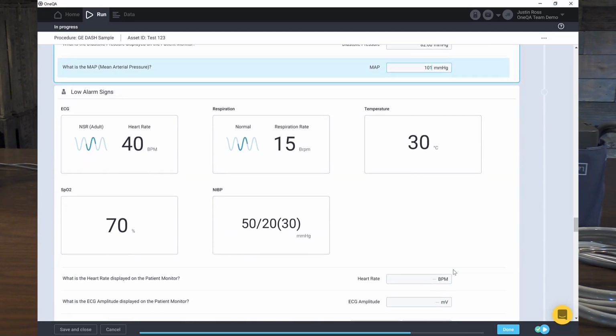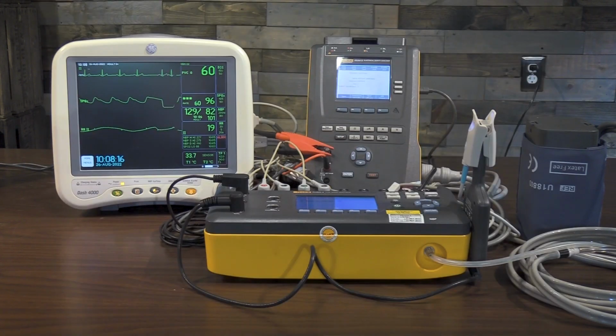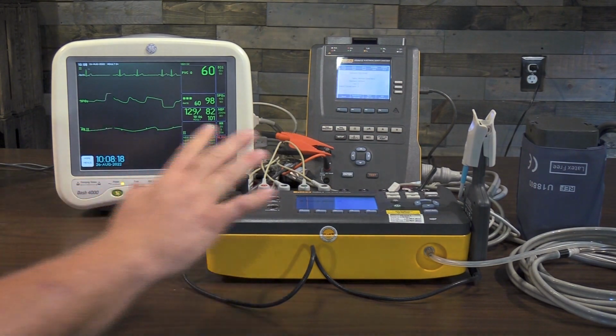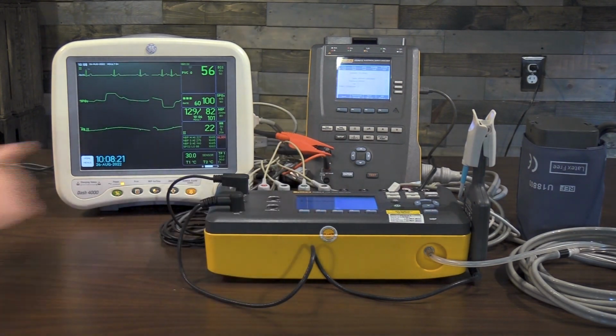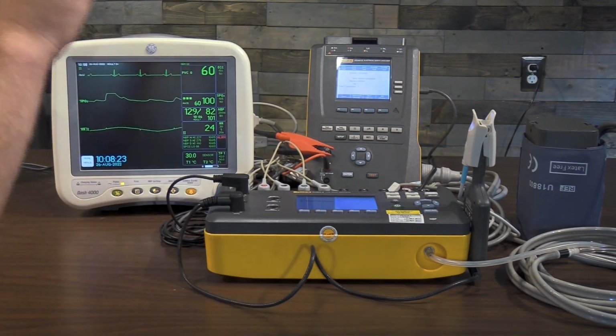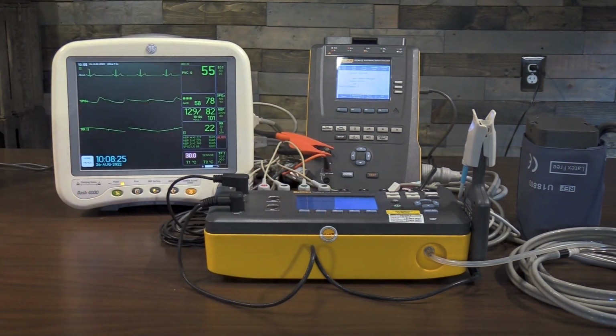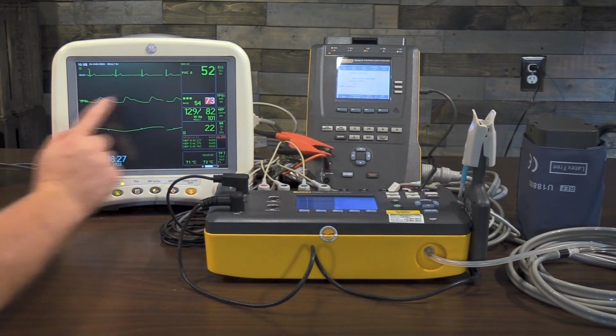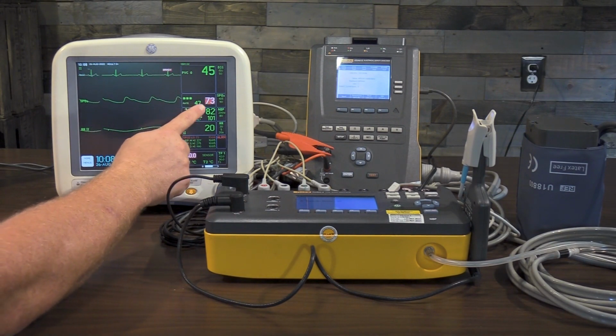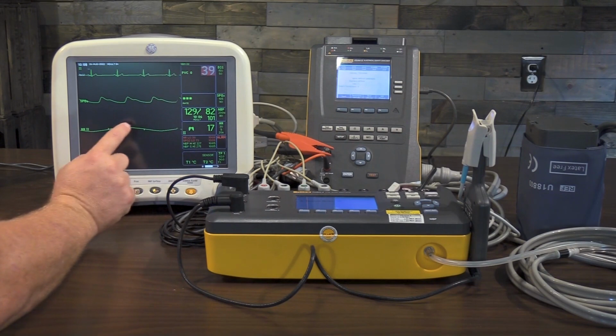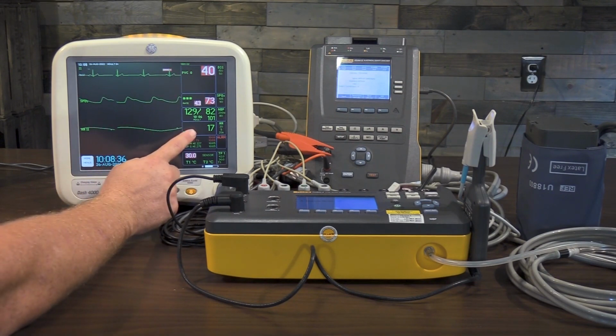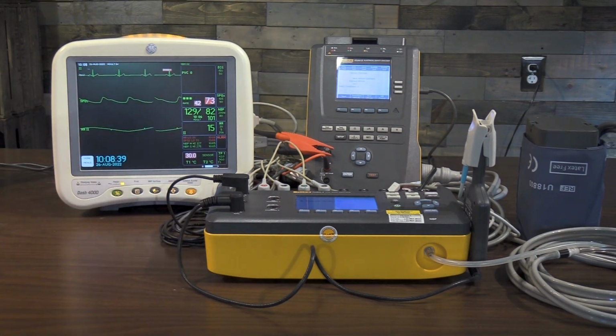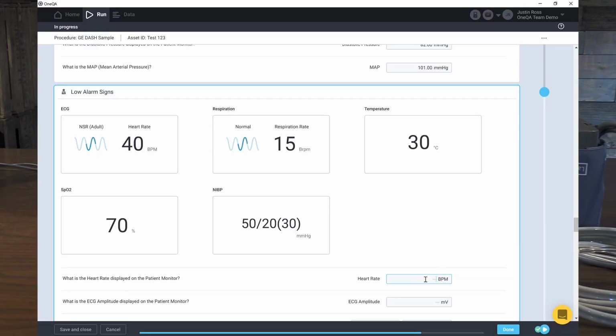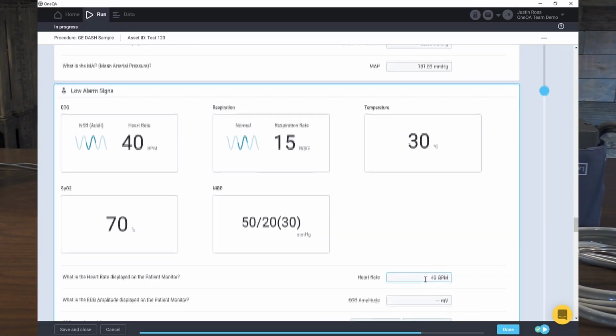Now let's see if we can trip all those low alarms. So here we go. We're going to click in here, and it's going to change all the parameters on the ProSim 8. Notice I didn't touch anything on this ProSim 8, and everything has changed. So I didn't even have to know how to set this up. Everything changed automatically for me. My heart rate's dropping. My respirations are dropping, so we're getting an alarm. My SpO2 is dropping. Here we go. So we have a heart rate of 40, and over here it's reading 40.